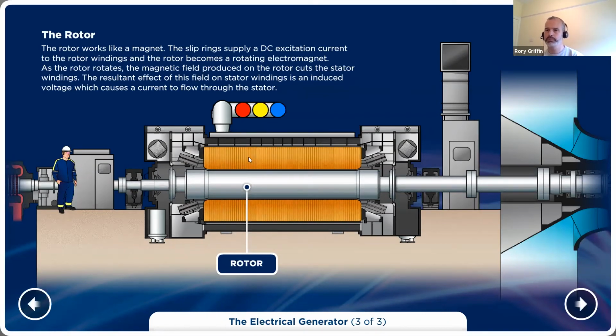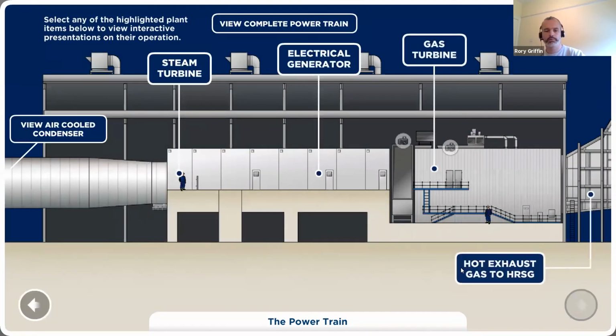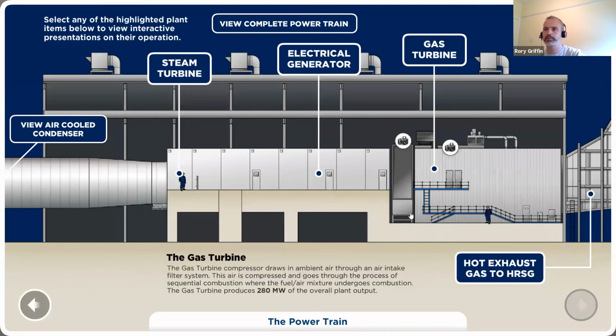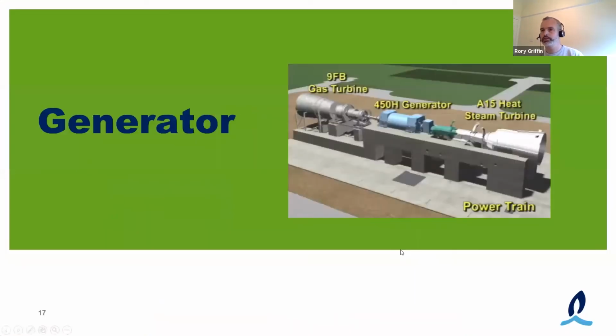The stator windings, they don't move, so they're called the stator windings. When the plant is synchronized to the grid, this has the electric field of the grid. So this is what connects to your 3 buses for 3 phases and is brought out to the step-up transformer to the grid. So what I'll do is I will finish now with this interactive. I'll just move back to the slides and give you a little bit more on electromagnetic induction.